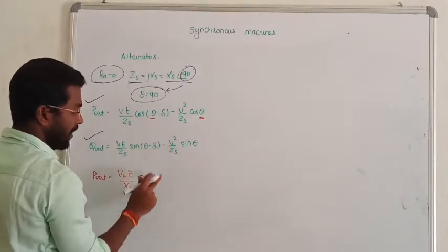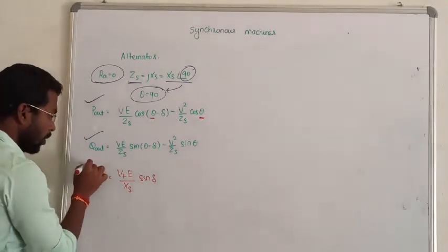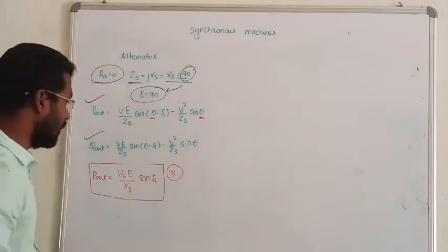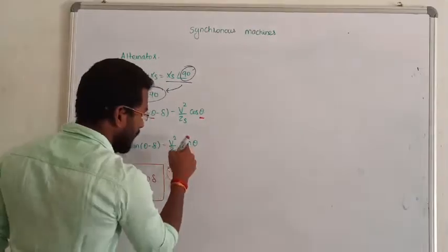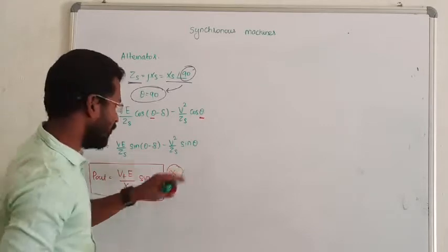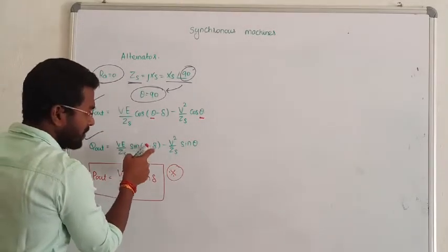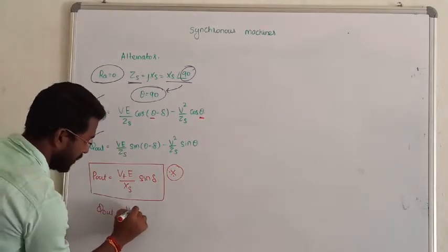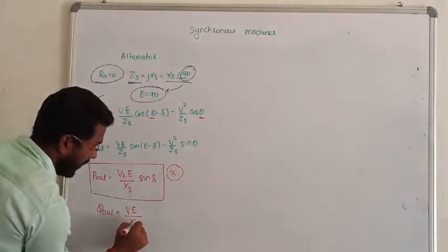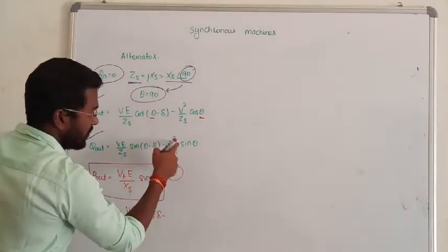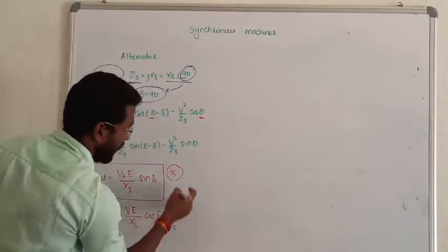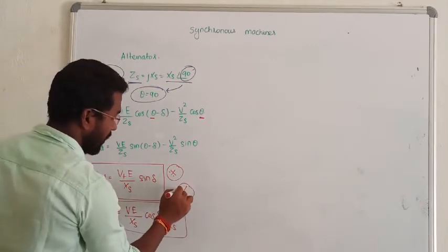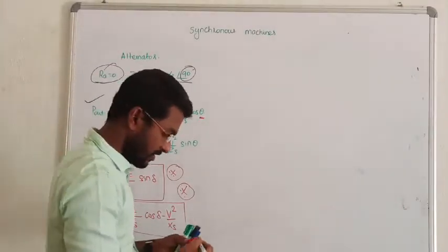This is the most generalized form of the real power output equation — that is very, very important, try to keep it in your mind. For the reactive power, when we make θ equal to 90 degrees, sin(90) is 1, and sin(90 − δ) gives cos(δ). So the output reactive power can be written as Q = (VE/Xs)·cos(δ) − V²/Xs.